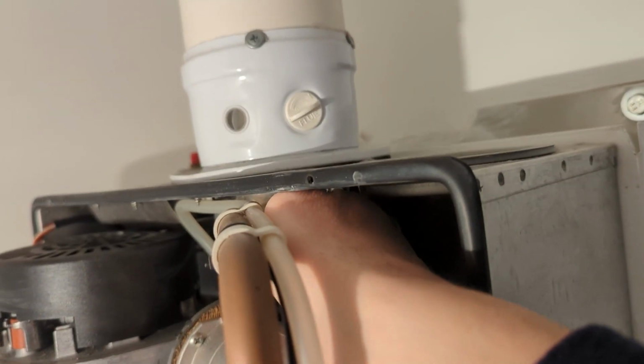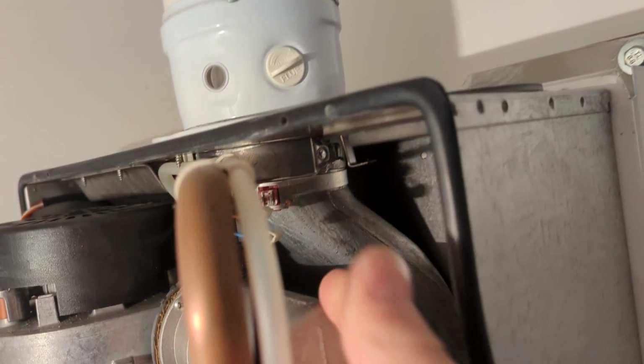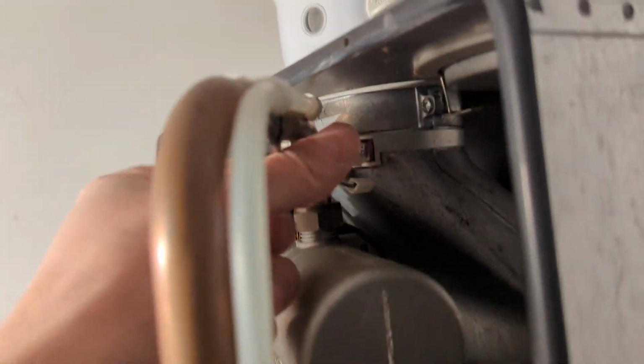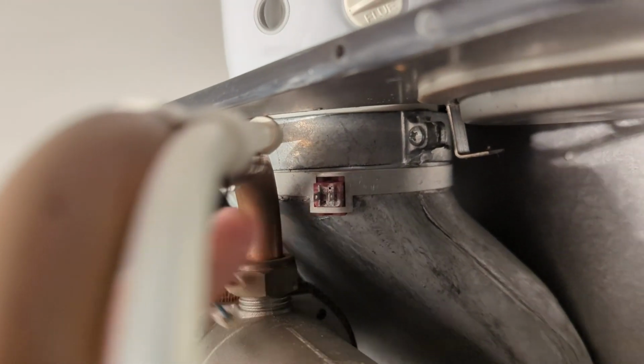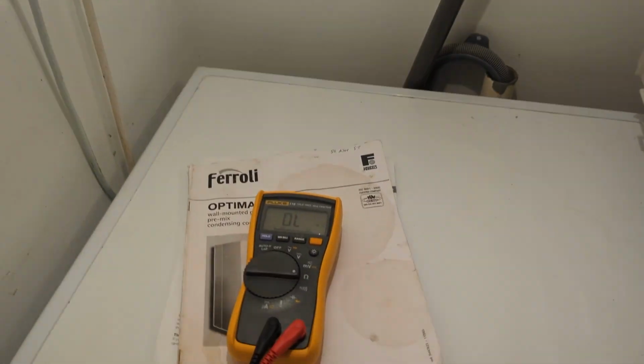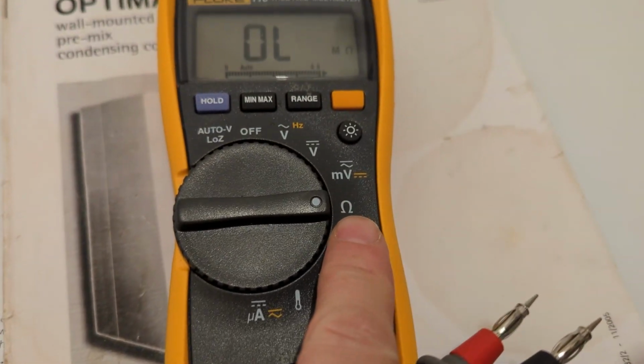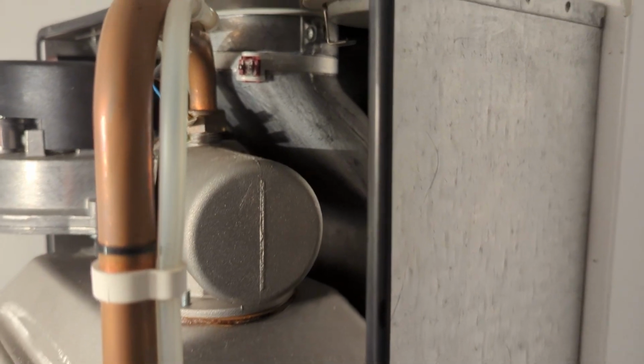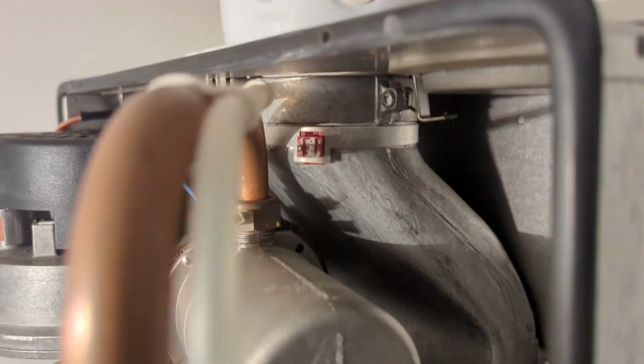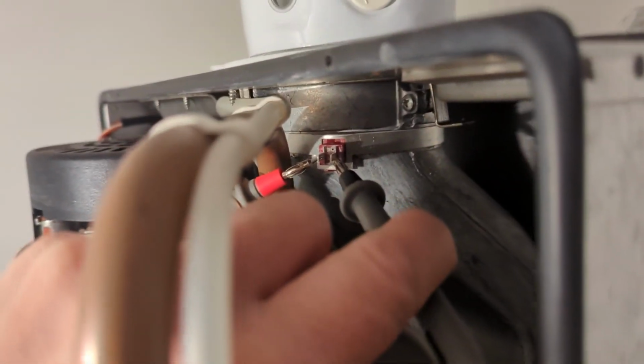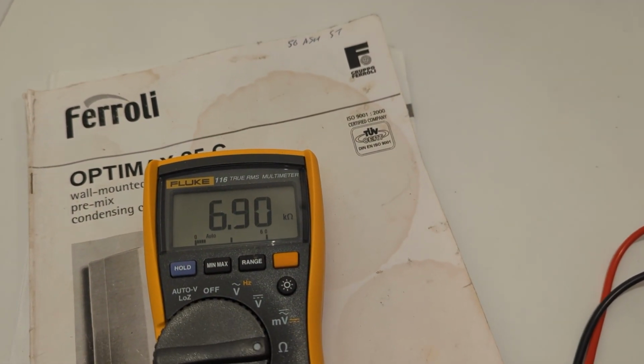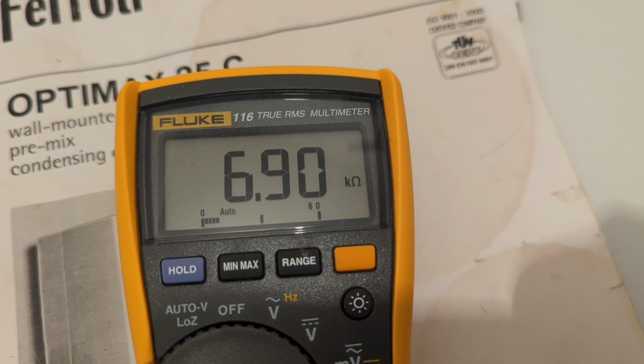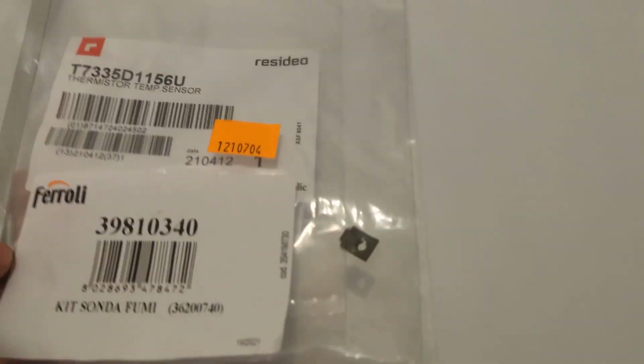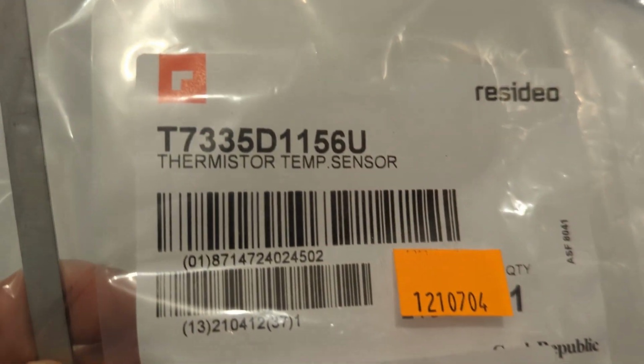If we unclip it, we can actually test that thermistor with the multimeter. We've got two little metal prongs there that we can put our multimeter on, and we can check it for ohms. As you can see on the multimeter there, we put it onto ohms. And we can check the resistance and see what the resistance equates to in terms of temperature. That is giving 6.9 kilo ohms, which basically equates to 34 degrees, which is too hot. It's not 34 degrees. So that tells me that is at fault.